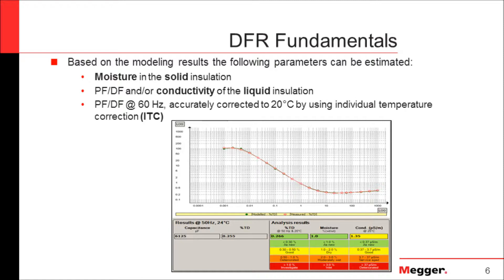Here is a typical screen of the software showing the dielectric response: the x-axis shows frequency, and the y-axis shows the power factor or dissipation factor value. At the bottom you will see the results — the measured capacitance, the measured power factor or dissipation factor, the corrected values to 20 degrees C, the moisture percentage, and the conductivity of the oil. Ultimately, we are looking at how moisture affects the service life of our transformer.